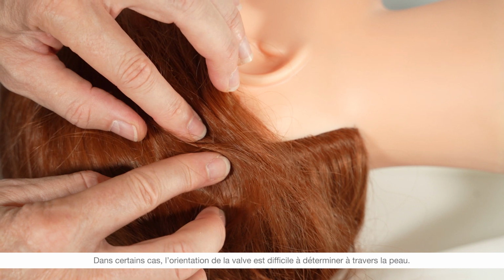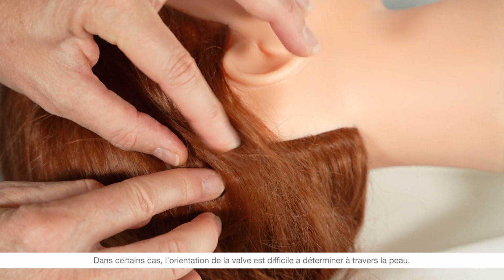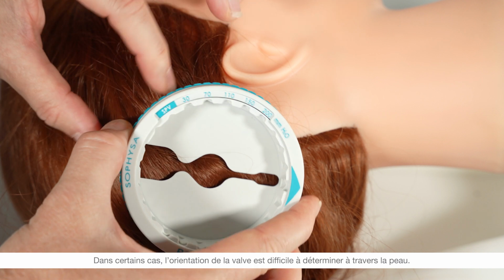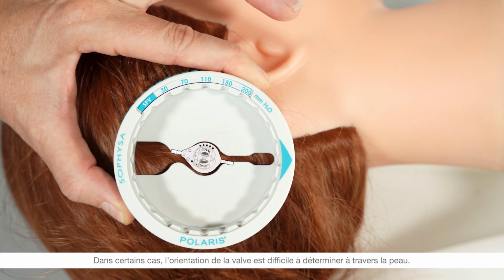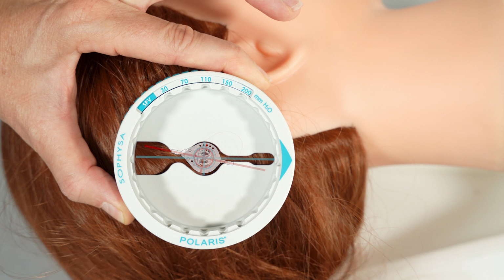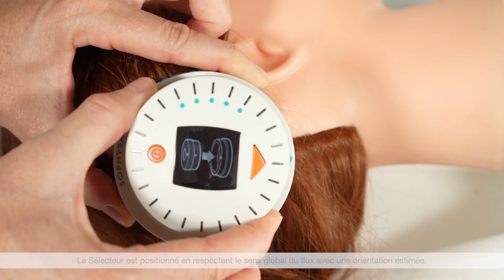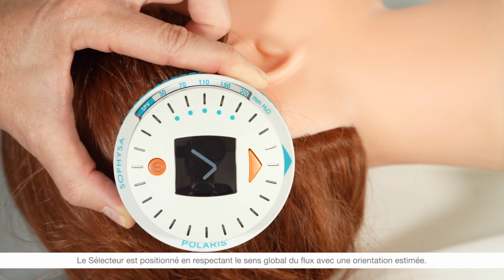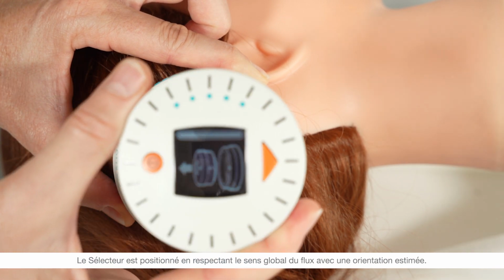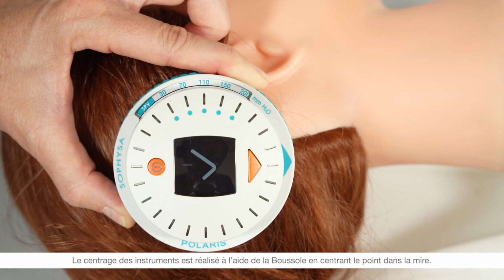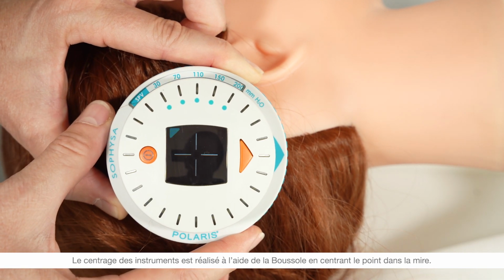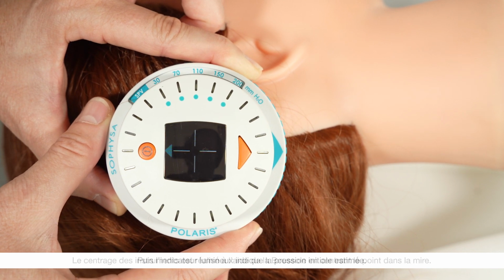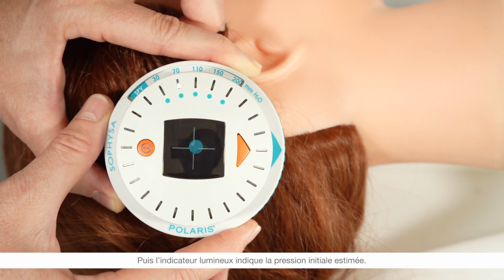In some cases, the connectors can be difficult to locate, which can make it difficult to accurately position the locator. In these situations, the stop method will help you position the instruments accurately in relation to the implanted valve actual axis. Position the locator again over the implanted valve with the direction of flow arrow properly oriented and center it using the compass. The compass will indicate the apparent current pressure setting of the valve.